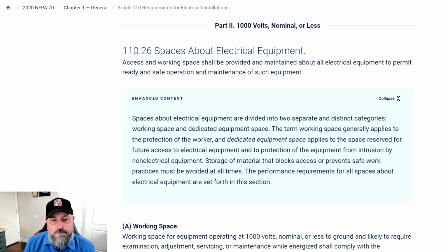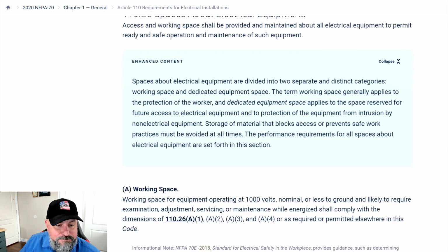Spaces about electrical equipment are divided into two separate and distinct categories: working space and dedicated equipment space. The term working space generally applies to the protection of the worker, and dedicated equipment space applies to the space reserved for the future access to electrical equipment and to protection of the equipment from intrusion by non-electrical equipment. Storage of material that blocks access or prevents safe work practices must be avoided at all times. The performance requirements for all spaces about electrical equipment are set forth in this section, right? So let's go into A, working space.